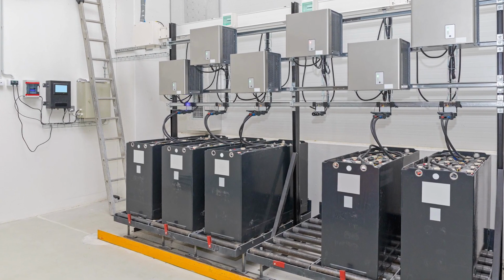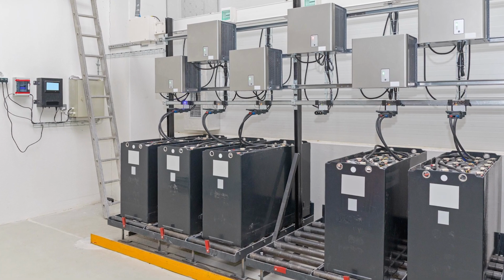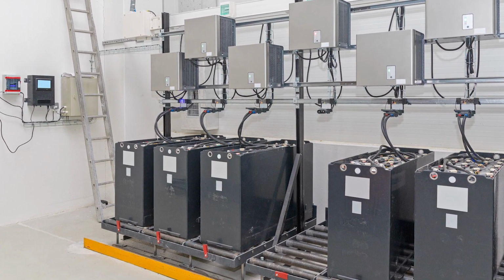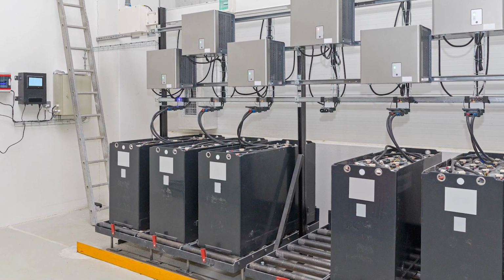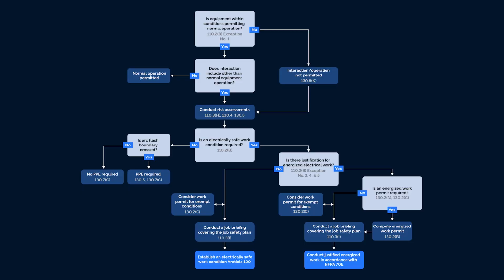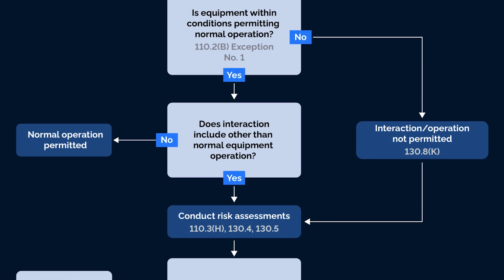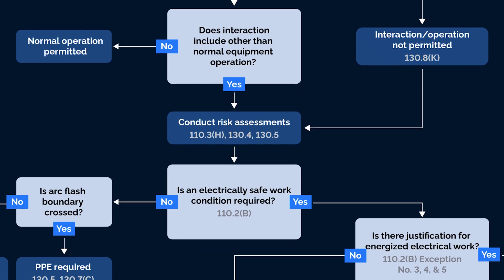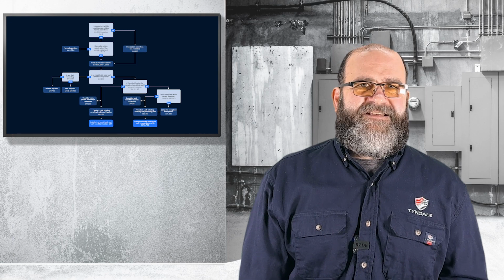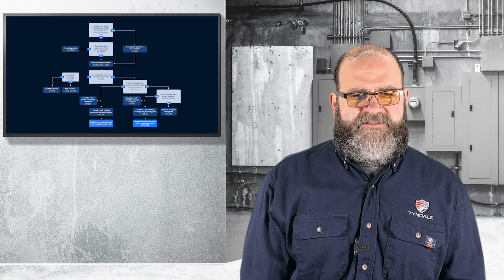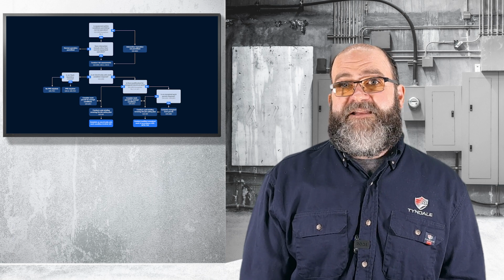Exception number 5 pretty much just reiterates that under 50 volts, de-energizing is not necessary as long as you have at least considered the capacity of that circuit and overcurrent protective device to make sure no explosion hazard exists. Forklift batteries. Big battery banks have a lot of energy available to them. There's a fantastic flow chart in the handbook and online at that NFPA link that I told you about earlier that can walk you through that process. It's Exhibit 110.1.